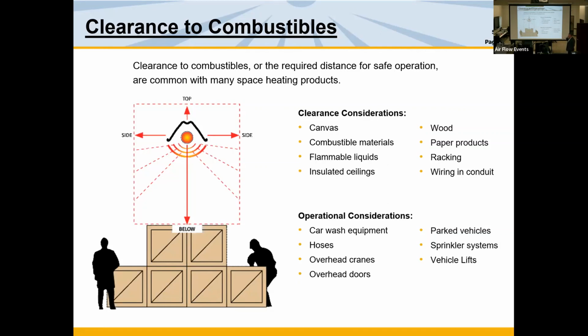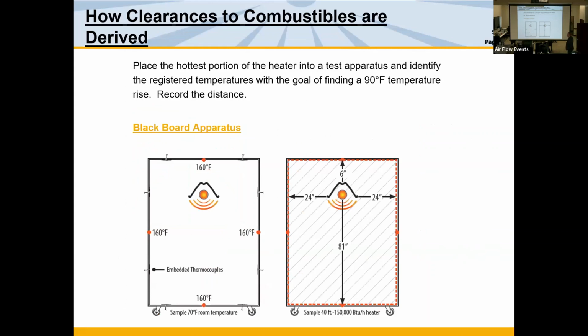How we get the clearances, on the next slide, please, is we hang a heater inside of an apparatus that's all painted black. Those of you who have been to our lab have seen it. It has thermocouples embedded throughout. We run the heater for 2 hours, and when we hit the saturation point, it doesn't get any hotter. We measure the distance at which we got a 90-degree temperature rise. So if the lab is 70 degrees, we stop recording when the thermocouples read 160. That's what the standard calls for. So when people ask what the temperature of the heater is going to be at 18 inches off to the side, 13 foot, I have no clue. We sometimes can run a test, but as to how the standard works, it's a 90 degree temperature rise. That'll give you a clue.